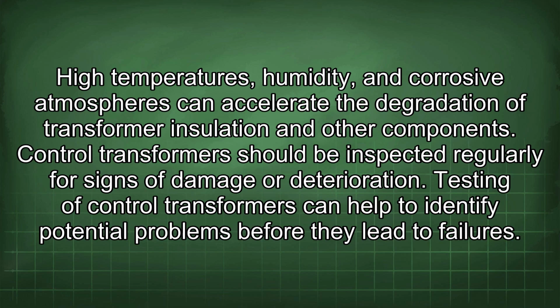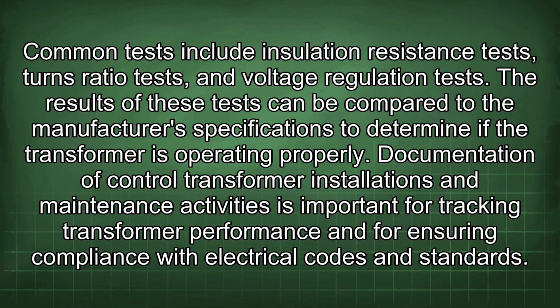Testing of control transformers can help to identify potential problems before they lead to failures. Common tests include insulation resistance tests, turns ratio tests, and voltage regulation tests. The results of these tests can be compared to the manufacturer's specifications to determine if the transformer is operating properly.